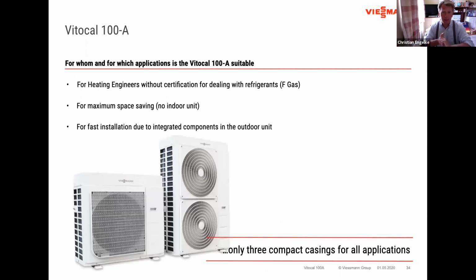So for whom is the heat pump? The 100A, as I said before, is ideal for heating engineers and installers who are not F-gas registered, who just want to, or come across inquiries now to, fit heat pumps, because obviously the world is talking about heat pumps everywhere. So this model is ideal for those people who are not really into F-gas registrations and certification. Small compact machines for the outputs available, and also no indoor unit to consider. So if you have reduced space requirements in properties with terrace houses, for example, or apartments, then that model will be quite attractive. And again, the installation can be quite fast and quick, because the majority of components are integrated in the outdoor unit.